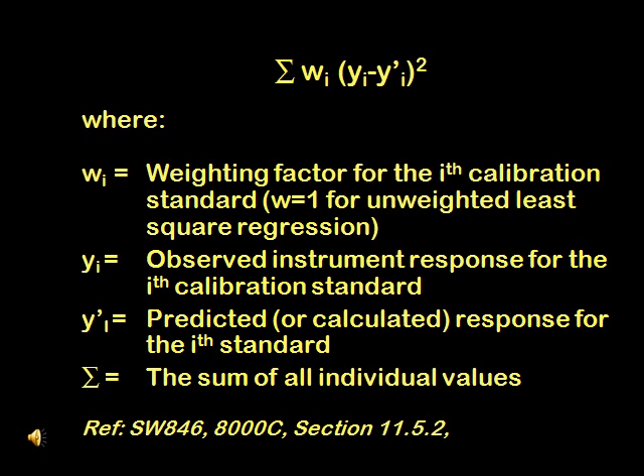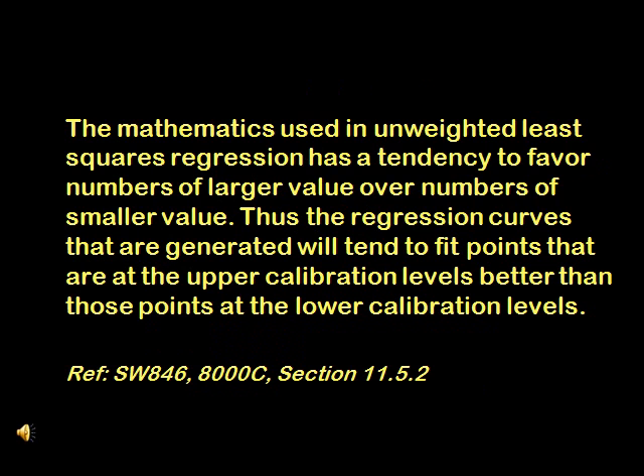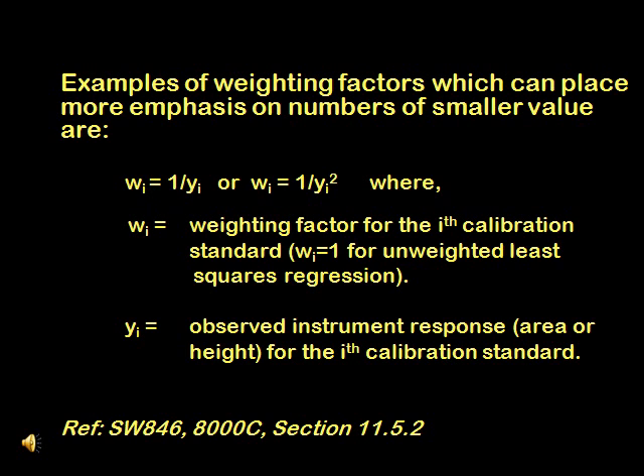The general form of the sum of the squares of the differences containing the weighting factor is shown in this slide. According to 8000C, the math used in unweighted least-square regression has a tendency to favor numbers of large value over numbers of smaller value. Therefore, the regression curves generated will tend to fit points at the upper calibration levels better than those at the lower calibration levels. To compensate for this, a weighting factor which reduces this tendency can be used. Examples of weighting factors which can place more emphasis on numbers of smaller value are given in this slide.